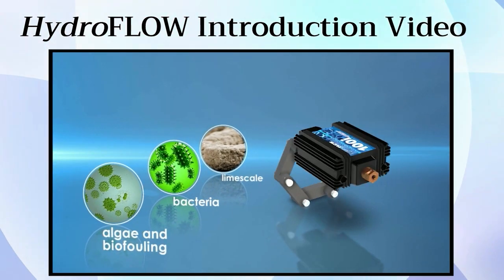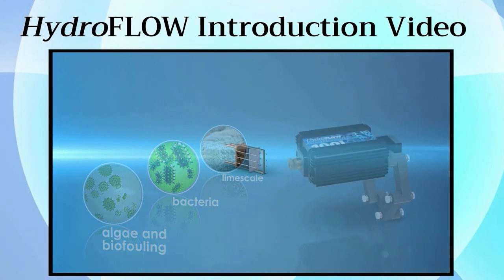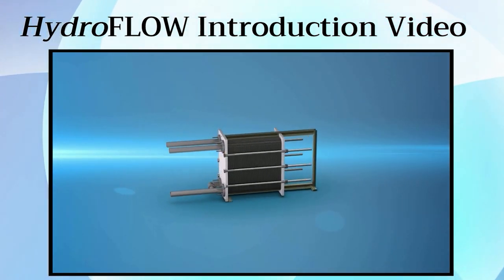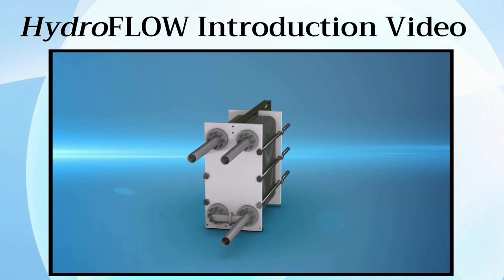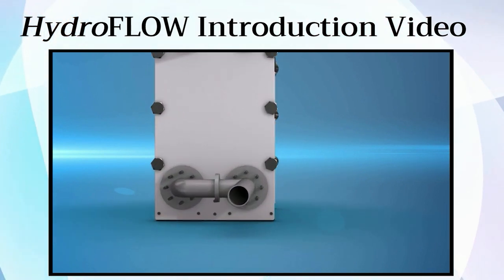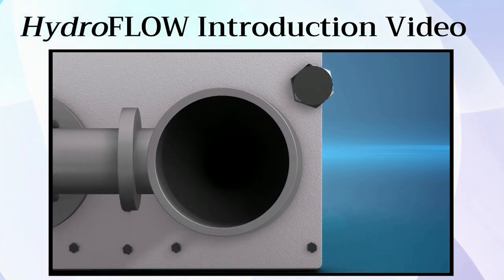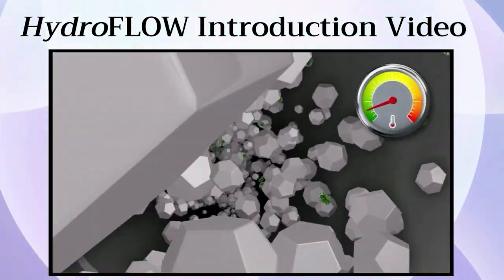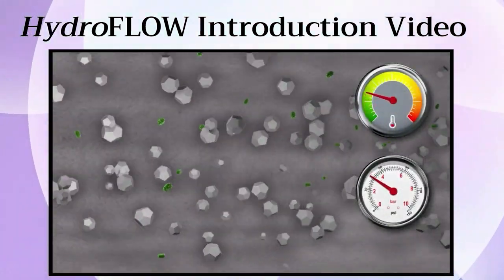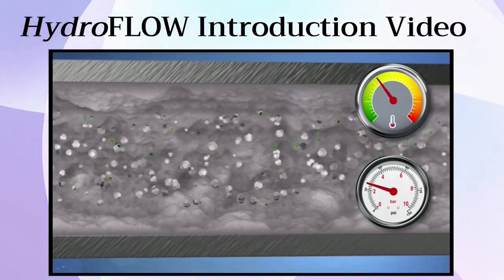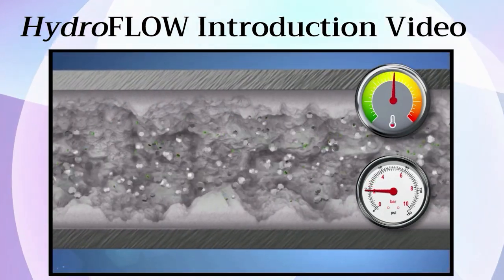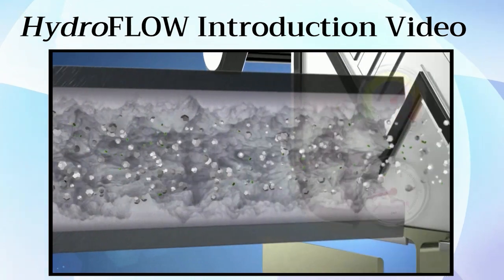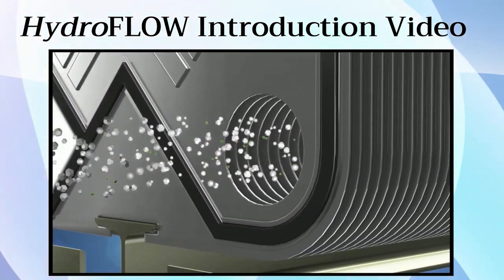Based on over 20 years of experience, HydroFLOW's environmentally friendly technology works with various process liquid systems. A liquefied solution inside a pipe system may contain minerals, such as calcium carbonate dissolved in the form of ions. When temperature increases or pressure drops, the solution becomes supersaturated, which causes the ions to adhere to piping and equipment surfaces in the form of scale.